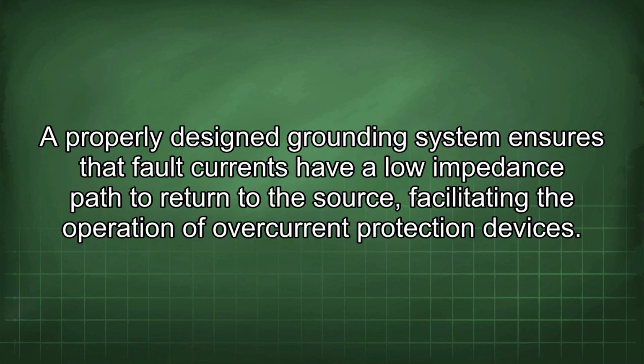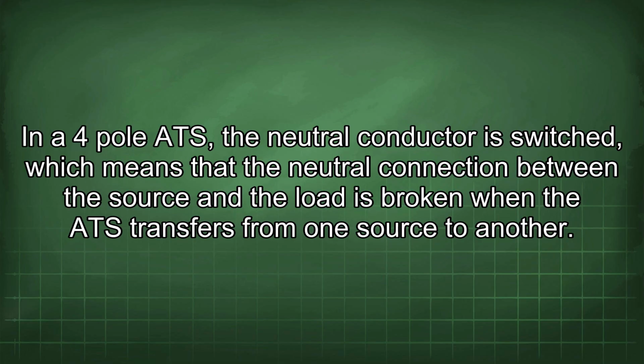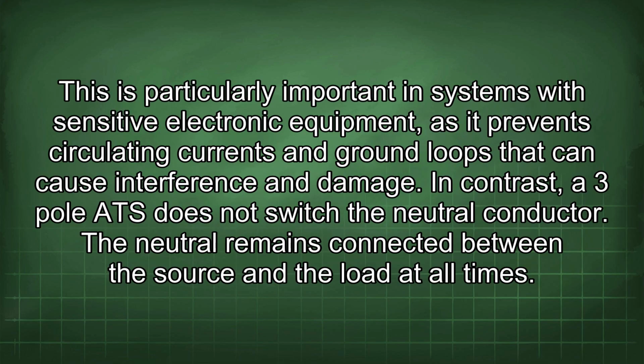A properly designed grounding system ensures that fault currents have a low impedance path to return to the source, facilitating the operation of overcurrent protection devices. In a 4-pole ATS, the neutral conductor is switched, which means that the neutral connection between the source and the load is broken when the ATS transfers from one source to another. This is particularly important in systems with sensitive electronic equipment, as it prevents circulating currents and ground loops that can cause interference and damage.